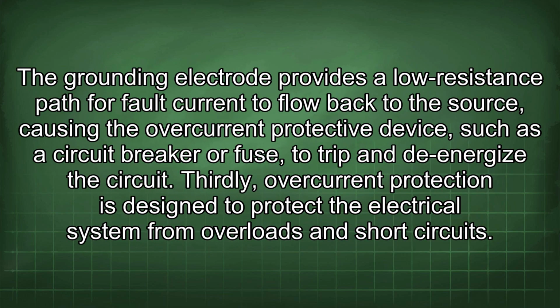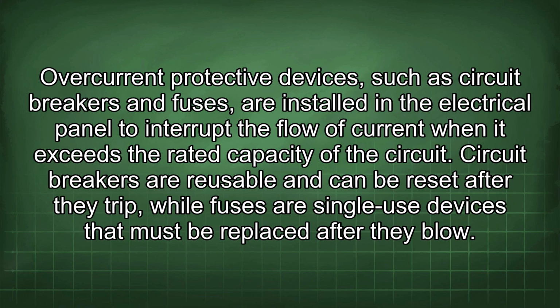The grounding electrode provides a low resistance path for fault current to flow back to the source, causing the overcurrent protective device, such as a circuit breaker or fuse, to trip and de-energize the circuit. Thirdly, overcurrent protection is designed to protect the electrical system from overloads and short circuits. Overcurrent protective devices, such as circuit breakers and fuses, are installed in the electrical panel to interrupt the flow of current when it exceeds the rated capacity of the circuit.